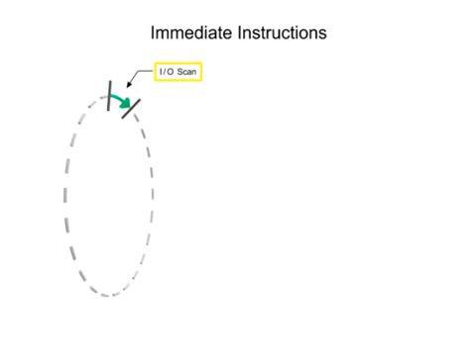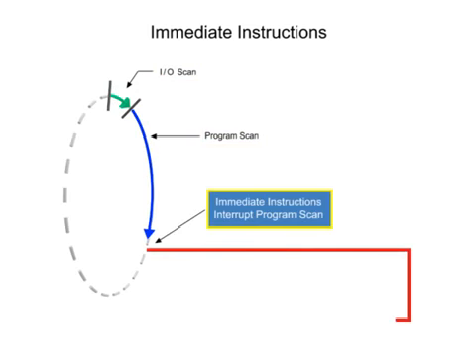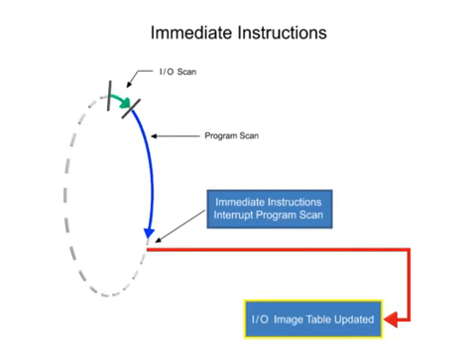For time-critical applications, immediate input and immediate output instructions are used to interrupt the normal program scan to update the current input or output image table.